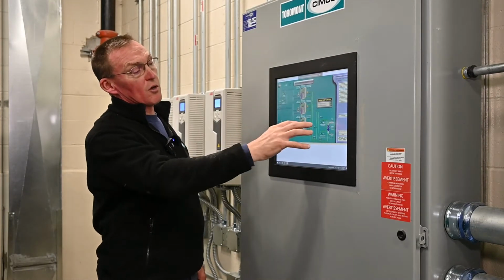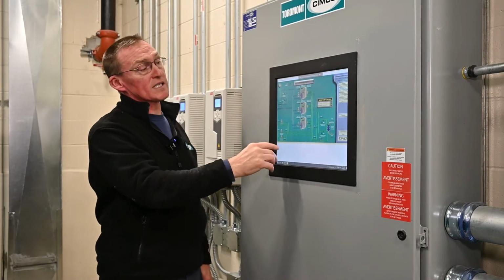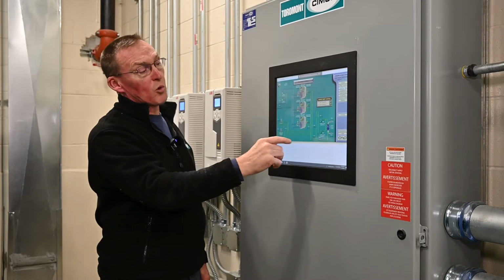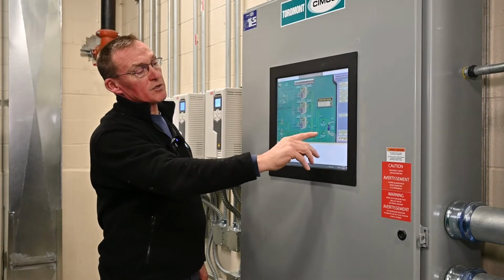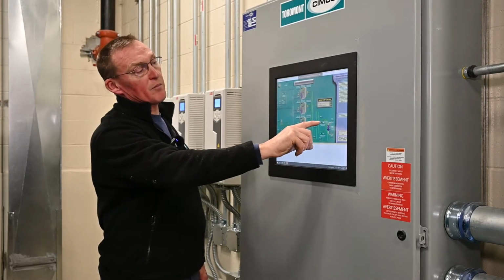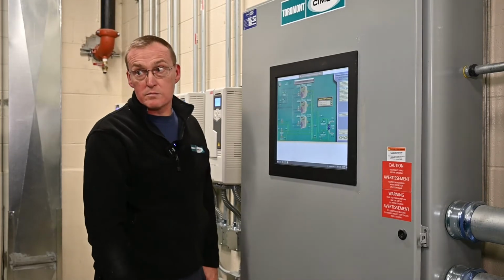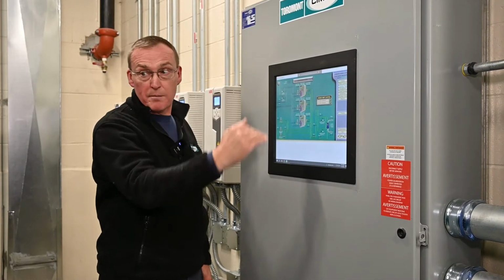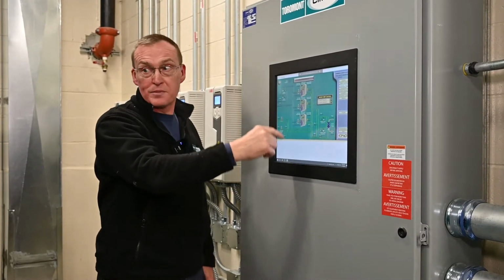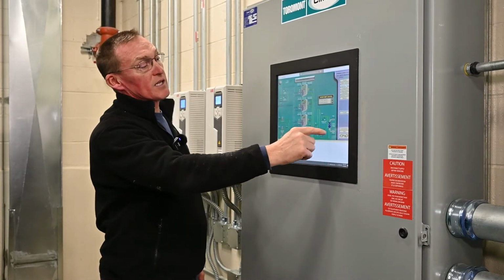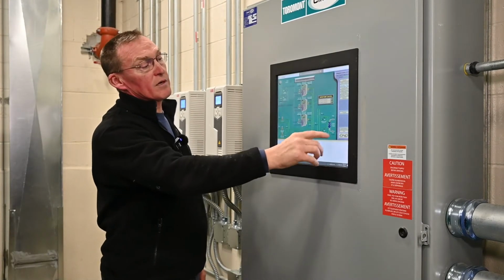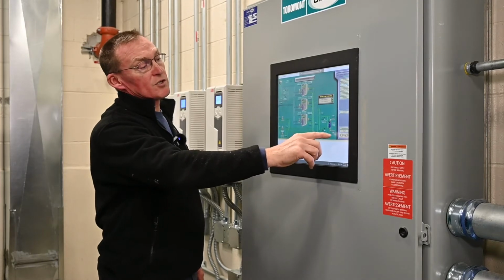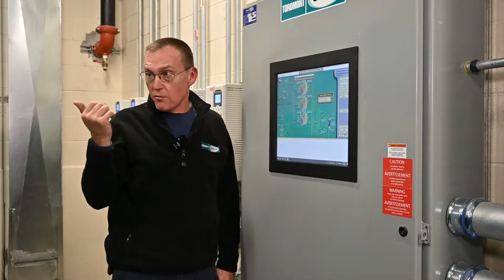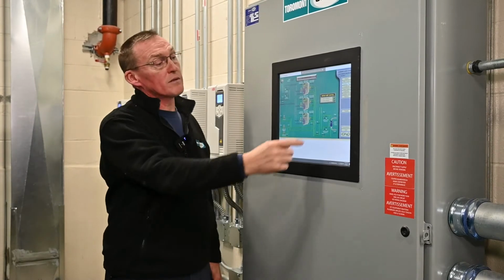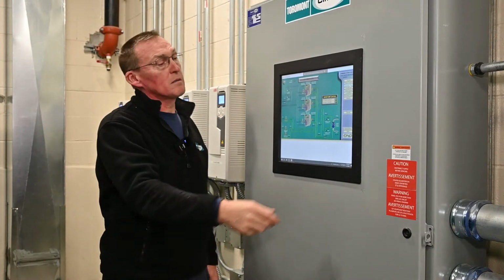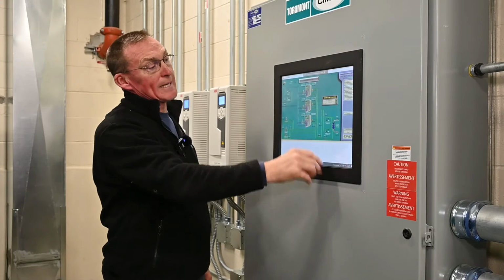We have sensors all over that we're monitoring at all times because that's how we base keeping this warm loop warm so that we can cycle, and you'll see the VFD speed come in above P3 or P4, whichever one we cycle, okay? And you'll see those speed up and speed down, maintaining that glycol loop temperature, right? That's your HX1 heat exchanger over in the corner over there, and this is water. TT20 is actually tank water temperature. In that far right side of that tank is a sensor down low. That's the actual water temperature coming back. And then this one's actually leaving the plate.